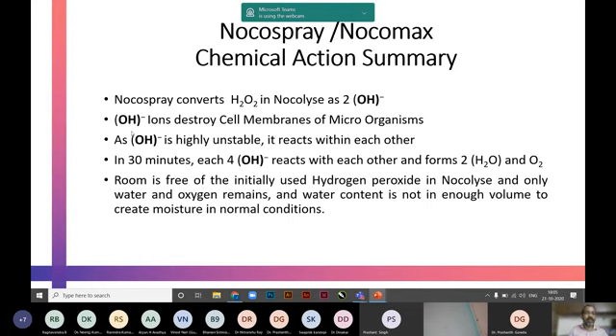These OH negative ions destroy all cell membranes of microorganisms, and OH negative is highly unstable. During the 30 minutes after the machine completes firing, it works destroying all microorganisms and converts back into H2O and O2. By the end of this time, the room is completely free of hydrogen peroxide, with no chemical content except O2 and water. So it becomes completely eco-friendly, with no chemicals, and microorganisms cannot gain any kind of immunity since no chemical remains.